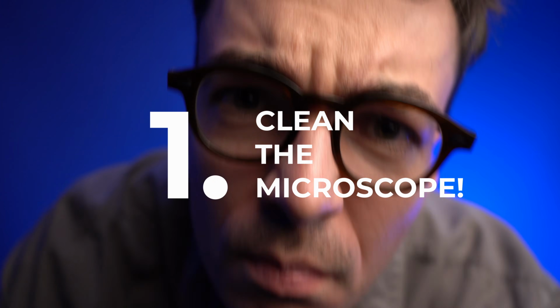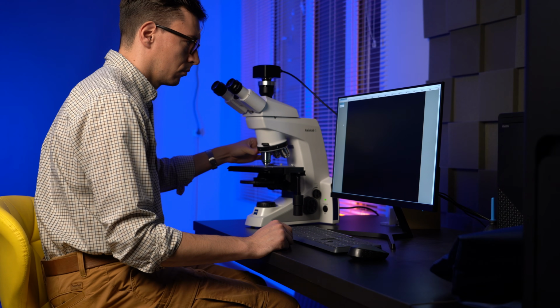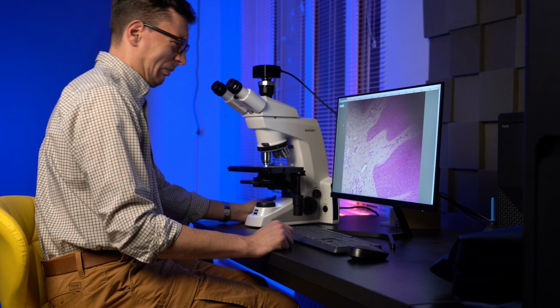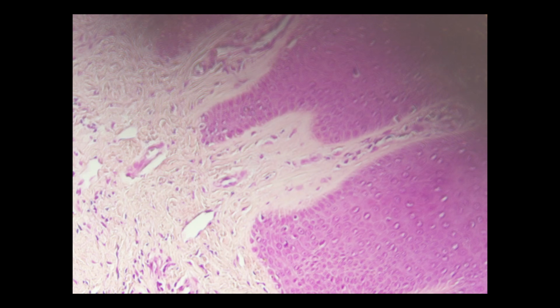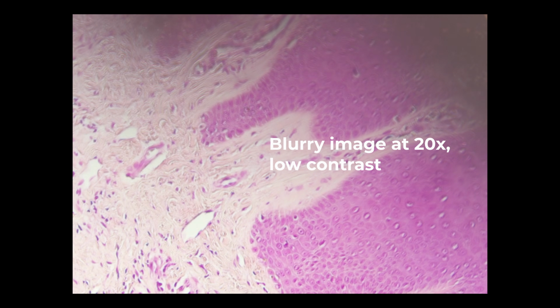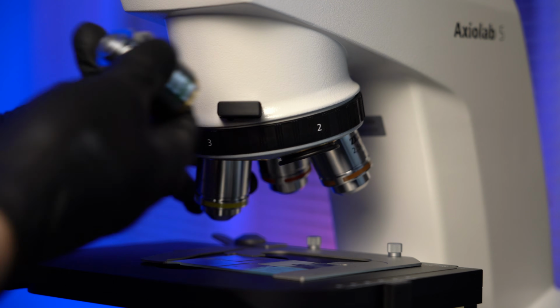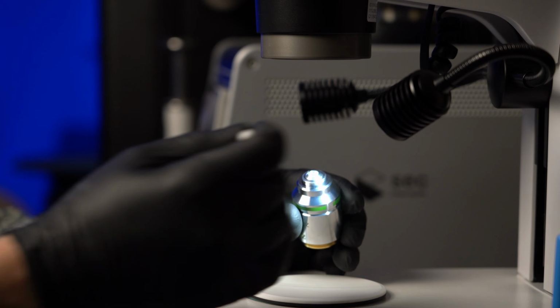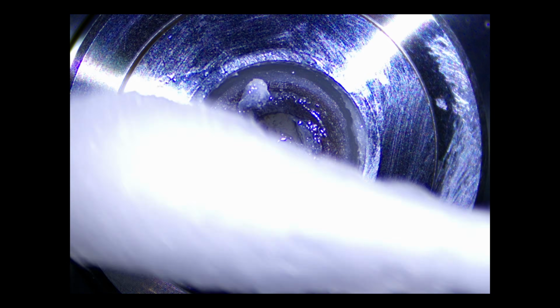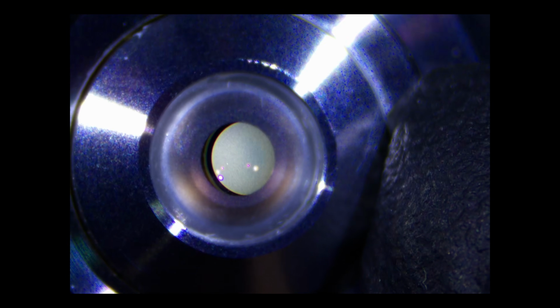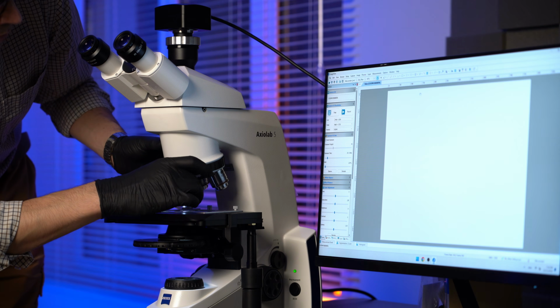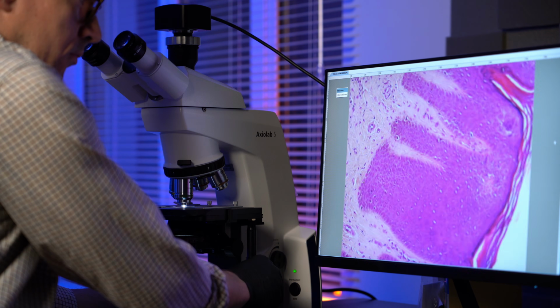Clean the microscope. The most important thing is the front lens of your objective. Contamination on it greatly affects the image quality. It can be immersion oil, chemicals, dust, or even organic materials. You should carefully clean it. Dust on other lenses mainly reduces image contrast and slightly affects resolution, but for sure all optical surfaces should be clean.